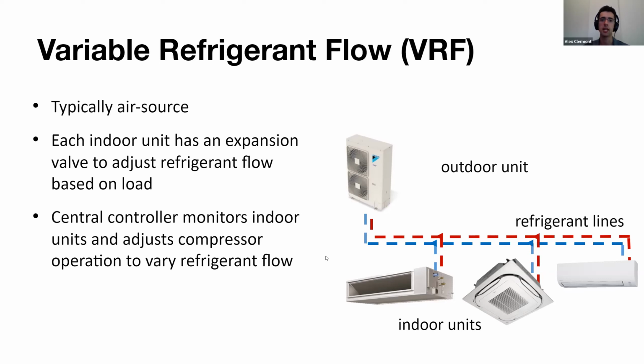Now, there are two different kinds of VRF: VRF heat pump and VRF heat recovery. Heat pump is also called a switchover system, and heat recovery is sometimes called a simultaneous system. What we're looking at here is a VRF heat pump system, where the entire system has to be in heating or cooling. Let's say the entire system is in cooling, each zone can modulate the amount of refrigerant it receives and cool more or less, but it can't go into heating. Again, heat pump systems are most common for small business applications, but sometimes VRF with heat recovery is also seen.